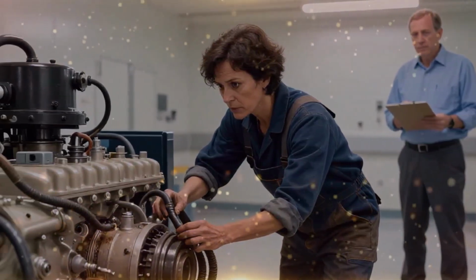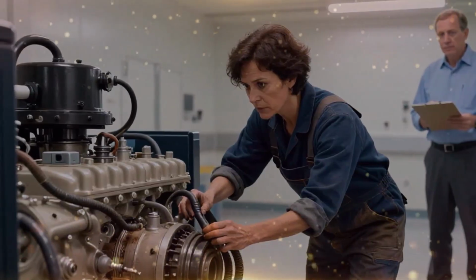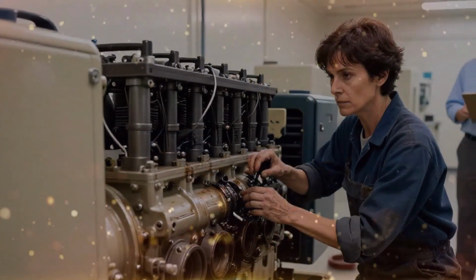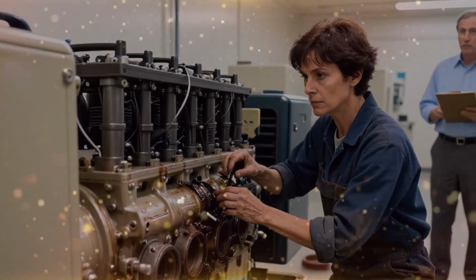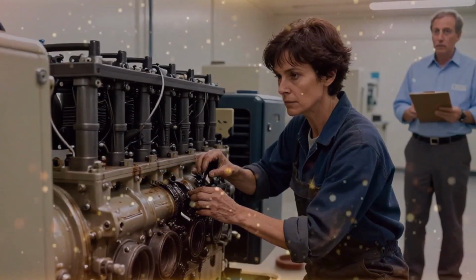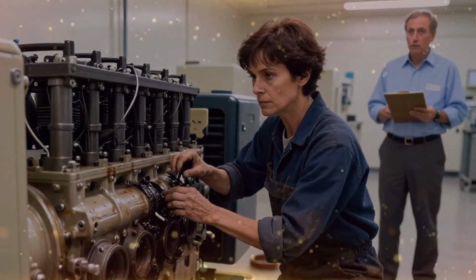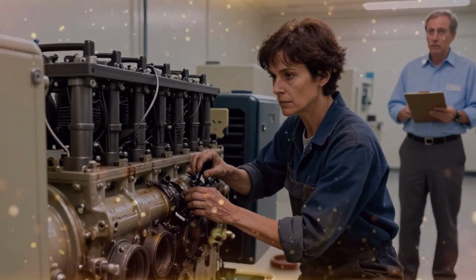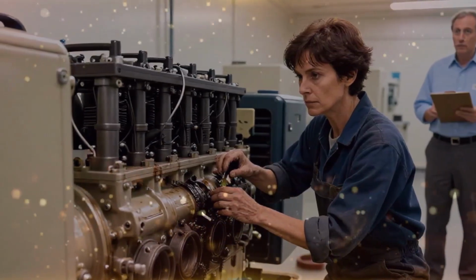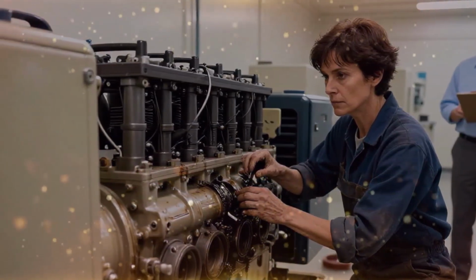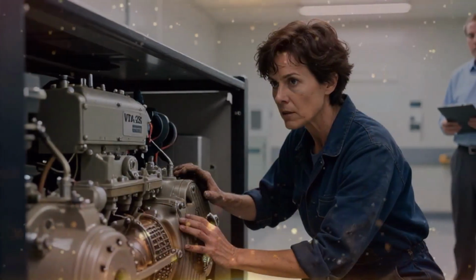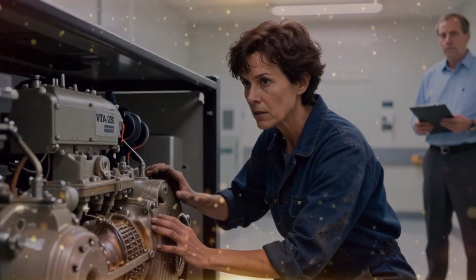This is your signal error, I told the manager, scraping a glob of the sludge away with my fingernail. The modern shop saw computer code that said the valve wasn't responding fast enough. They thought the electronics were slow. The truth is, the valve was trying to move, but it was suffocating, trying to pull hydraulic fluid through a wall of mud.